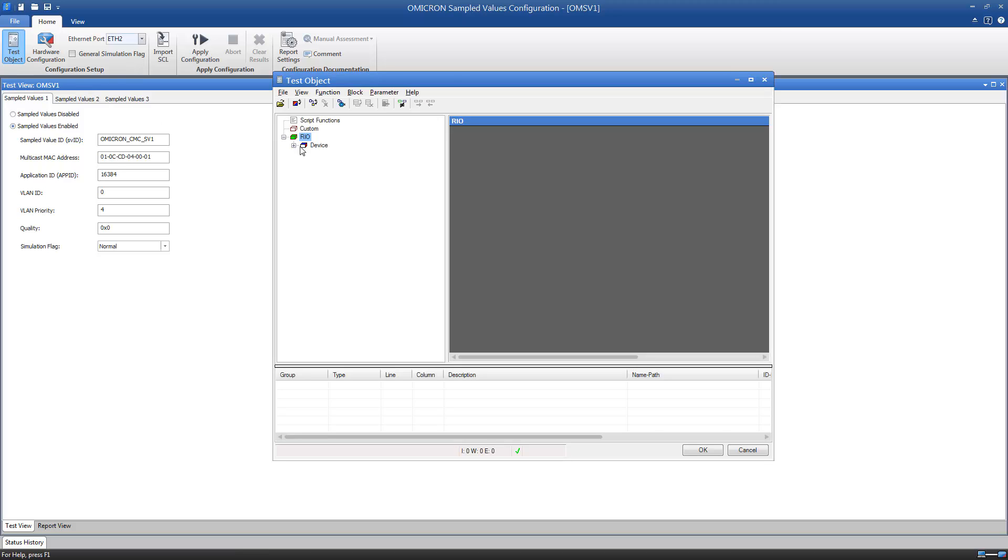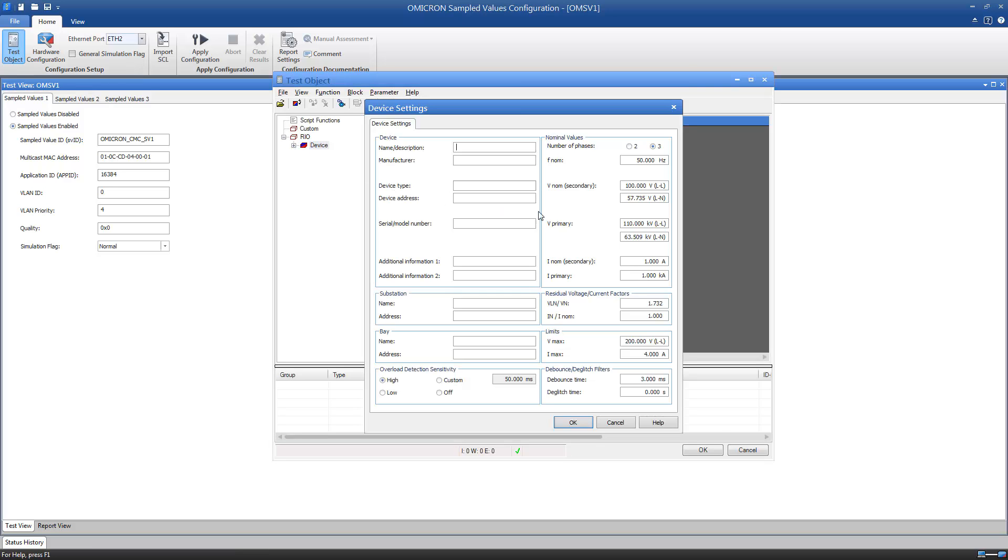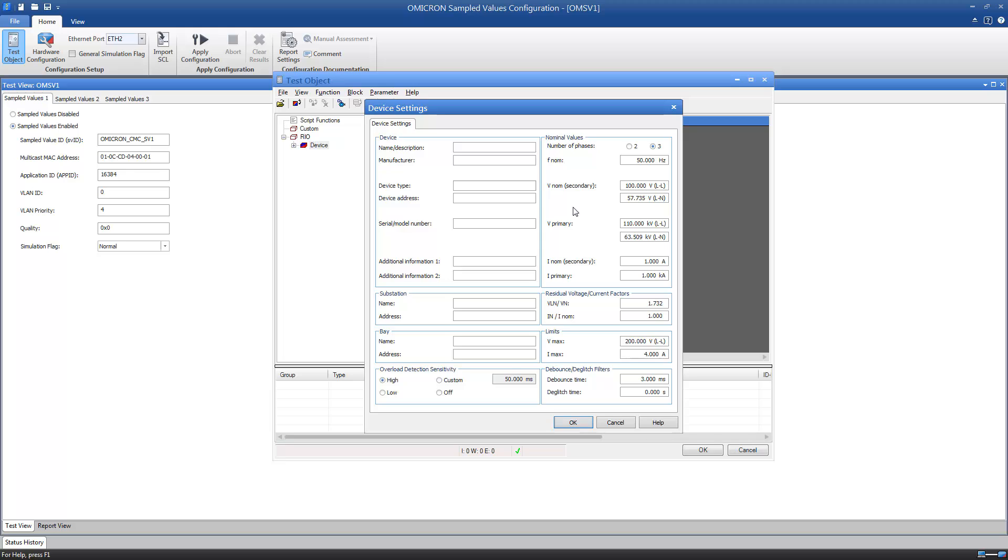It is important to enter the correct CT and VT ratios in the test object, as sampled values are always published as primary values. Also, the nominal frequency must be set correctly, as it influences the stream's sampling rate in some cases.